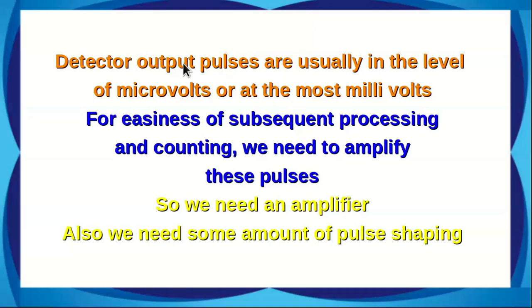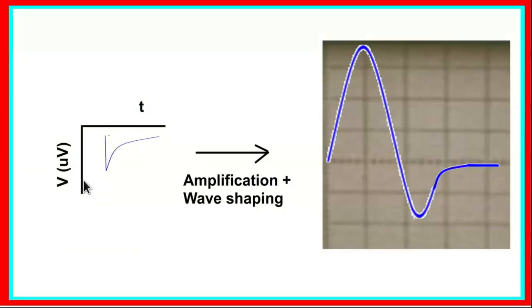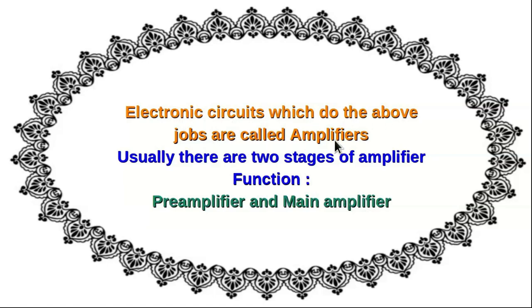Detector output pulses often do not have a suitable pulse shape for later processing, so pulse shaping is also needed. The detector output pulses — on the order of microvolts — are passed through appropriate circuits for amplification and pulse shaping, yielding well-formed signals. The electronic circuits performing these jobs are called amplifiers. There are two stages: a pre-amplifier, which immediately follows the detector output, and a main amplifier connected to the output of the pre-amplifier.